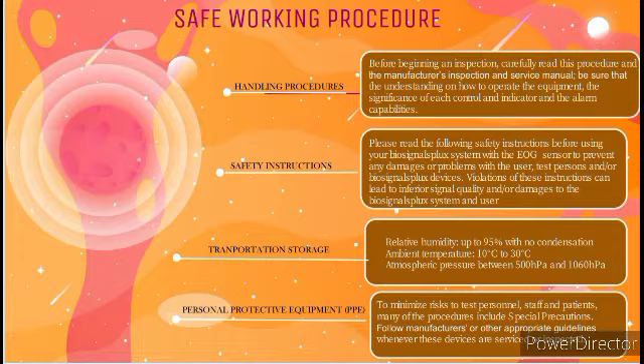Biosignalsplux device. Violation of this instruction can lead to interference with signal quality and damage to the biosignalsplux system and user. Number 3. Transportation storage. Relative humidity up to 95% with no condensation. Ambient temperature 10 Celsius to 30 Celsius. Atmospheric pressure between 500 HPA and 1060 HPA.